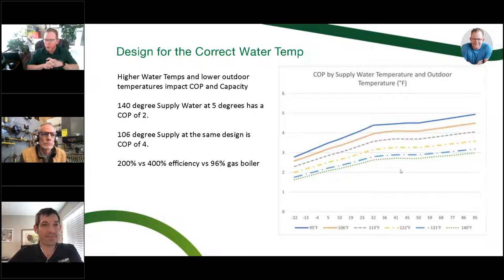So we need to be totally aware of what we're doing with the equipment, and truly understand what it means as we increase that water temperature. If Max designs a system around 95 degree water, he's going to have a COP in excess of 4. If I go in with no design, with 12 boxes just slapping them on the wall, and I'm running that thing at 140, that unit might have an advertised COP of 5 at 57,000 BTUs. I've inadvertently turned it into a 20,000 BTU unit, and my COP might be 1.5. Somebody's going to call you in January and say, why am I freezing? It's simply not heating the house because we didn't design it around the right temperatures.